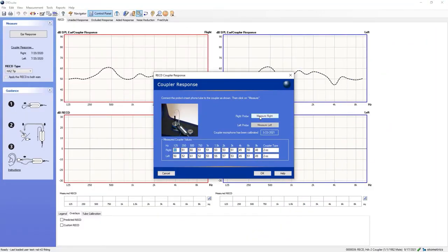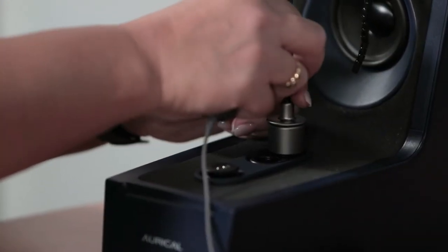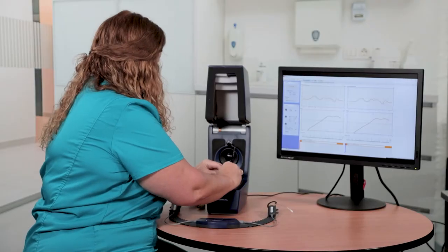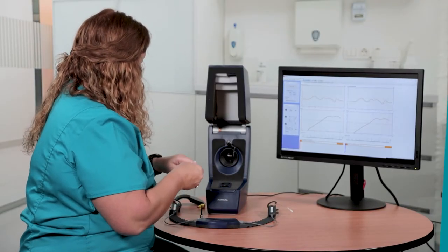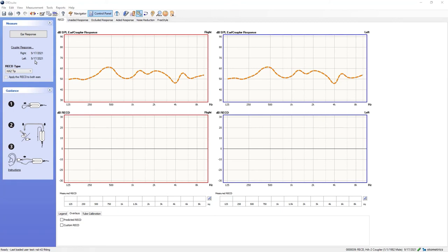Click the Measure Right button to complete the right probe coupler response. When the measurement is finished, repeat the appropriate setup for the other side. Click the Measure Left button. Click OK to close the dialog box. Remove the RECD coupling from the HA coupler and remove the FreeFit probe from the Aurical HIT test chamber. You will now see the updated coupler response in the control panel, showing the date of measurement.